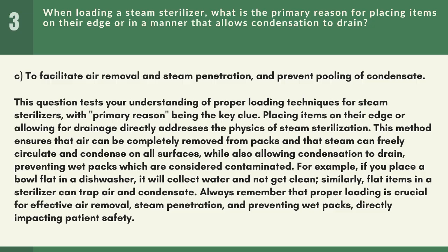For example, if you place a bowl flat in a dishwasher, it will collect water and not get clean. Similarly, flat items in a sterilizer can trap air and condensate. Always remember that proper loading is crucial for effective air removal, steam penetration, and preventing wet packs, directly impacting patient safety.